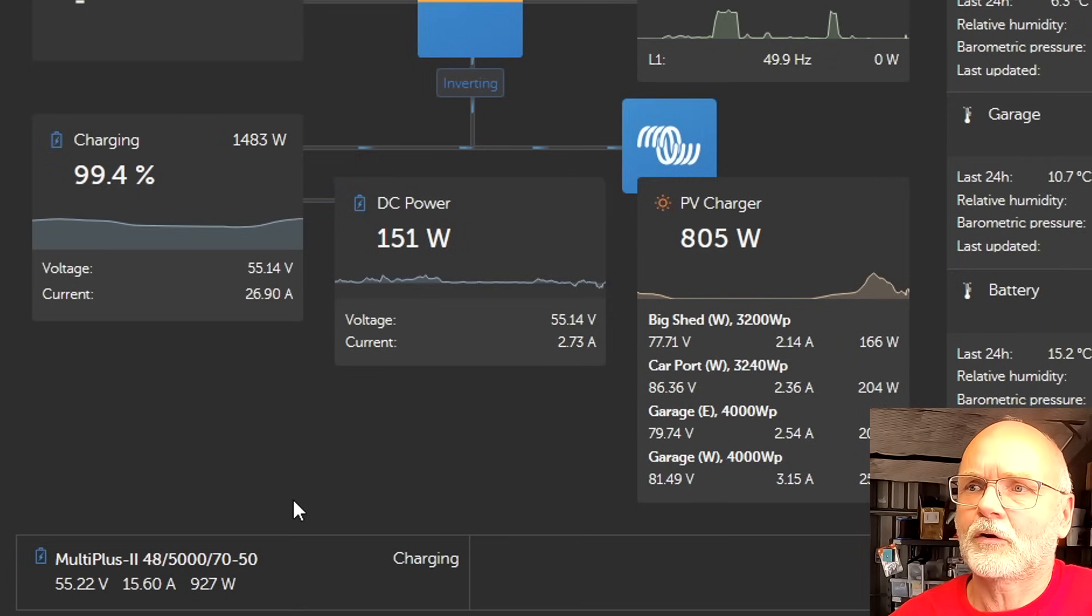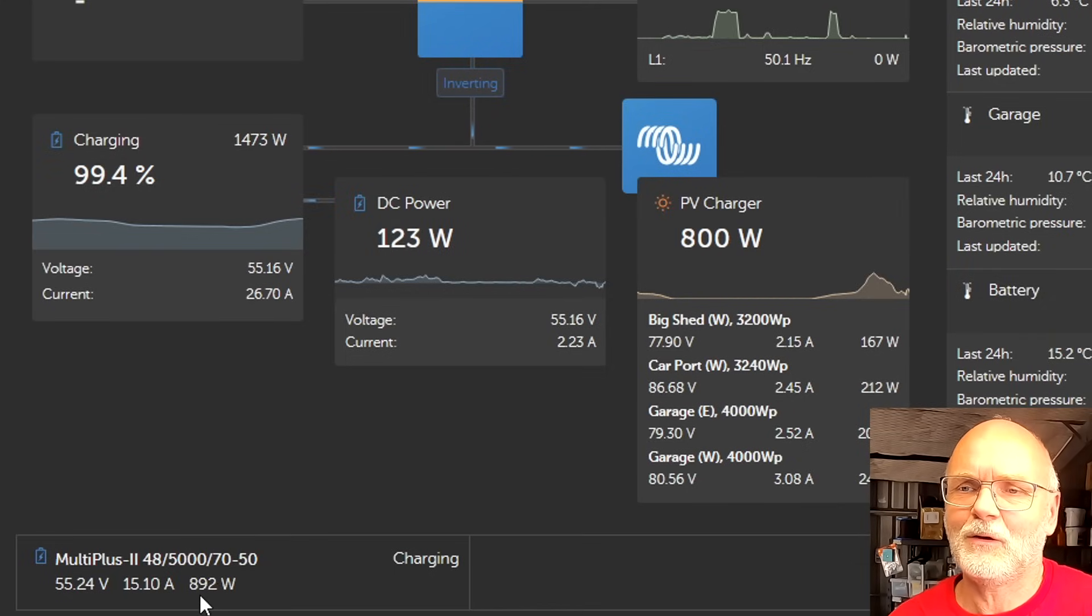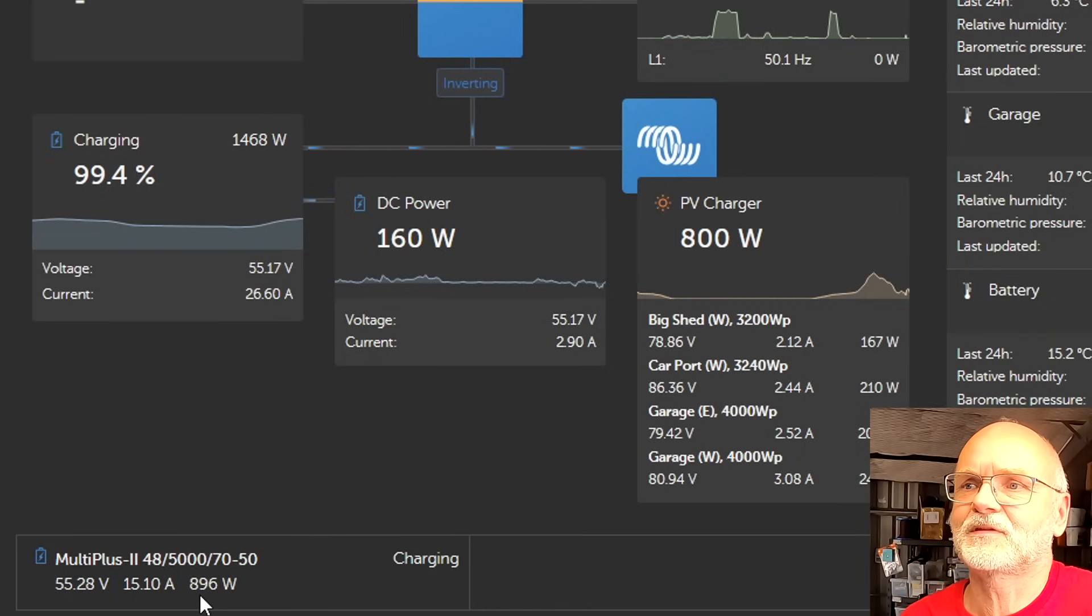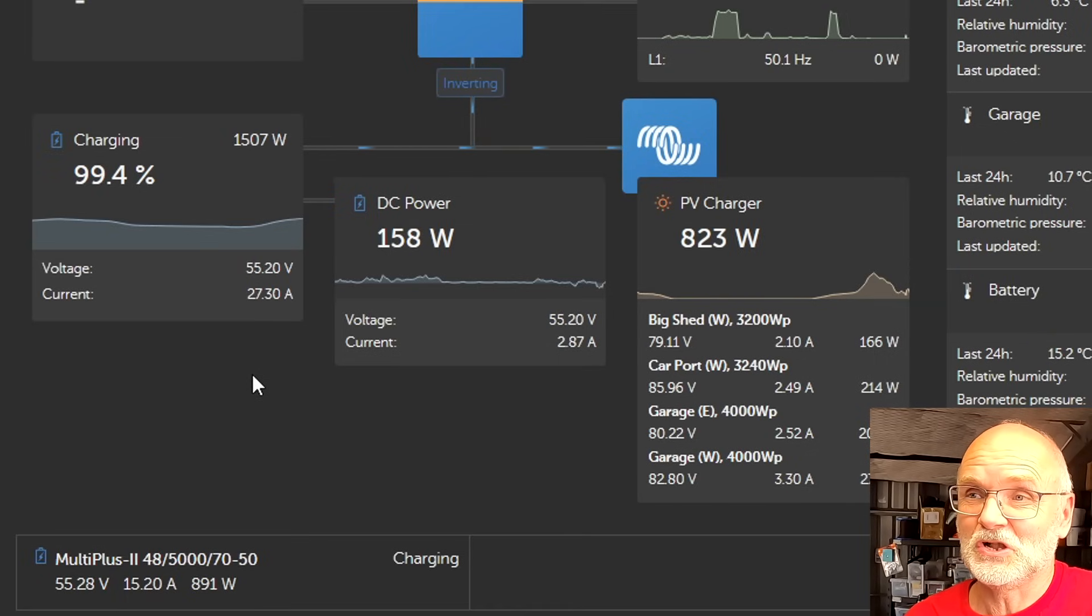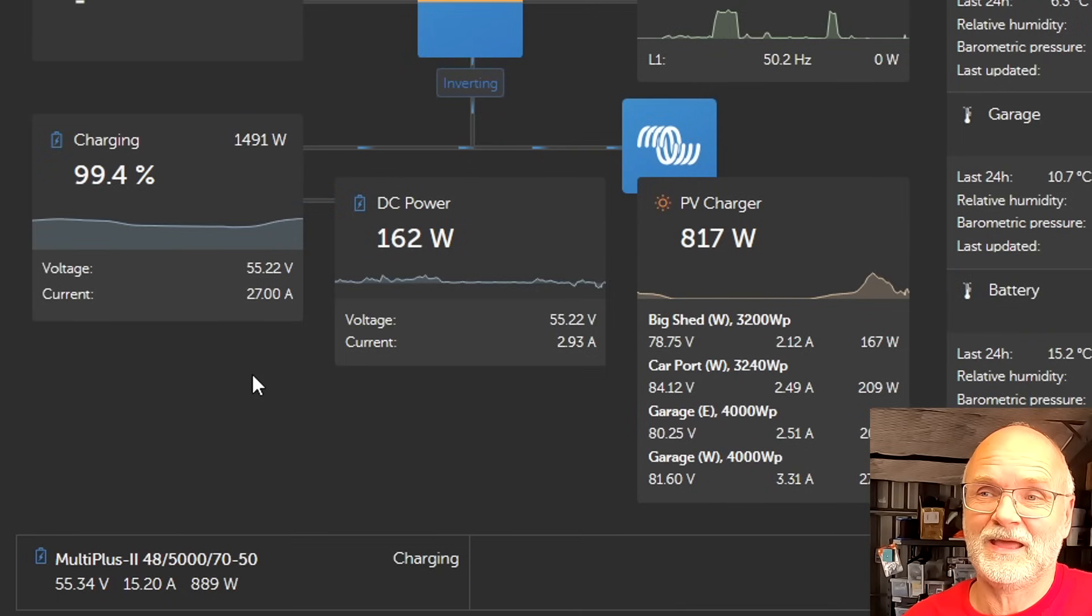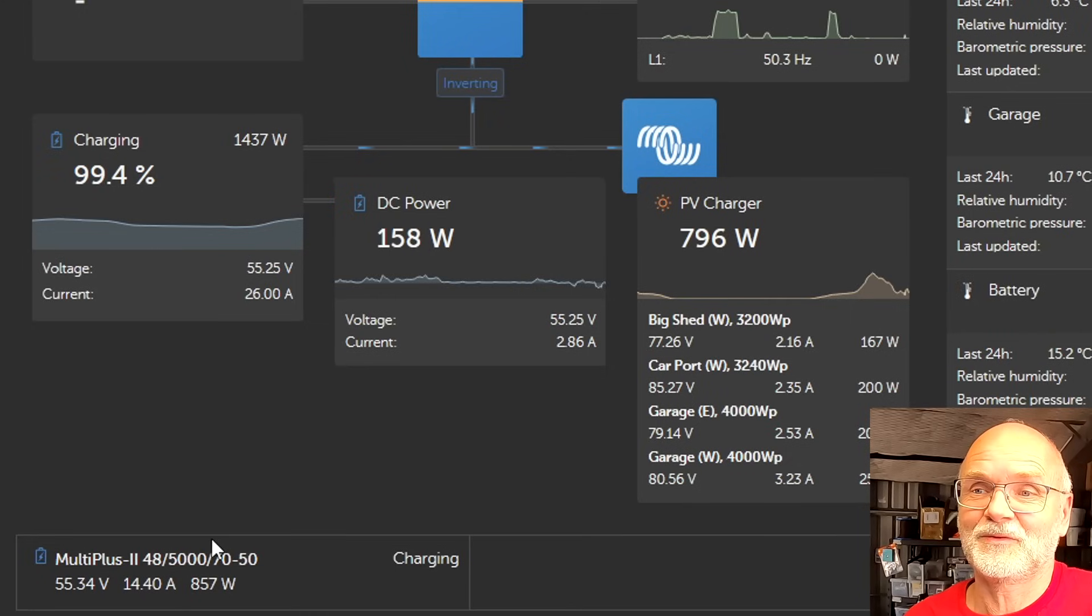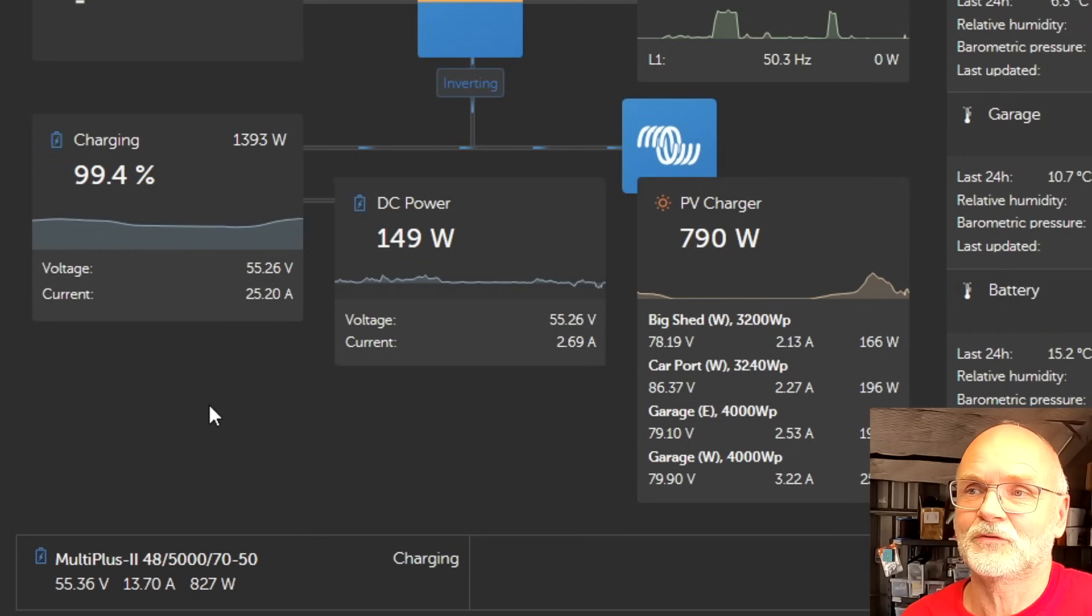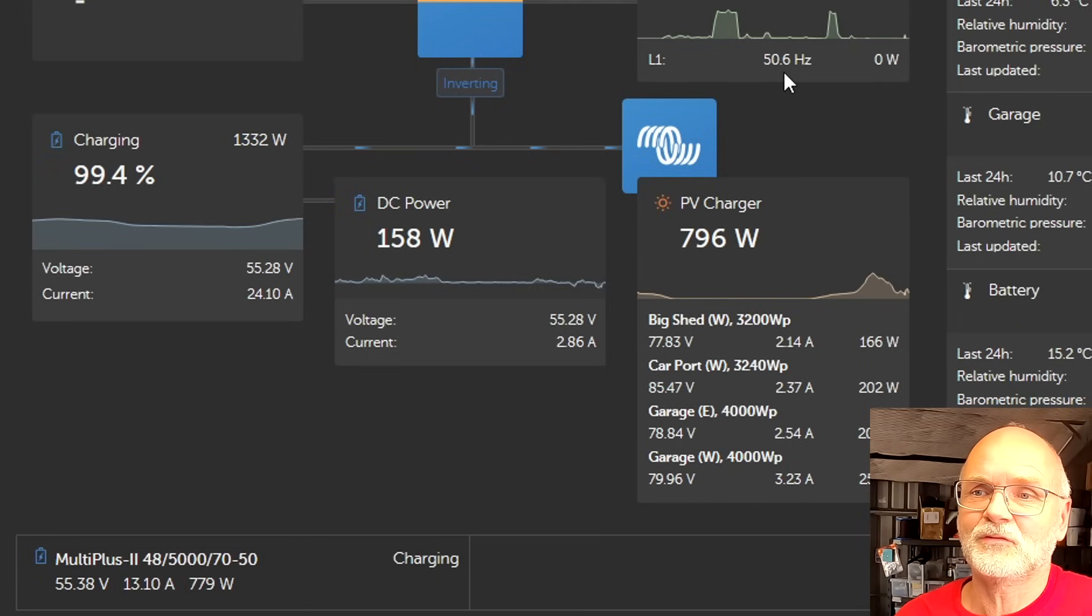It goes back to 50 hertz and then the solar charger kicks in again - look at this, full power, one kilowatt from the tilt system again, recharging the battery with 26 amps. So it waits until the frequency is normal to 50 hertz again and then it fully kicks in. I'm keen to see the curve of the tilt system later on and see if we can see that in the power output. Because we are over 55.2 volts already, the frequency is increasing again and the power output of the tilt system is decreasing again.